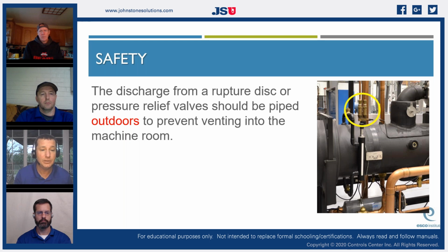And, you know, that makes sense. If I have a high pressure ruptured disc on my system, I don't want it inside the building. I want it outside. So we actually add those. And even our standard refrigeration systems that are using R404A, we actually have a high pressure rupture disc.